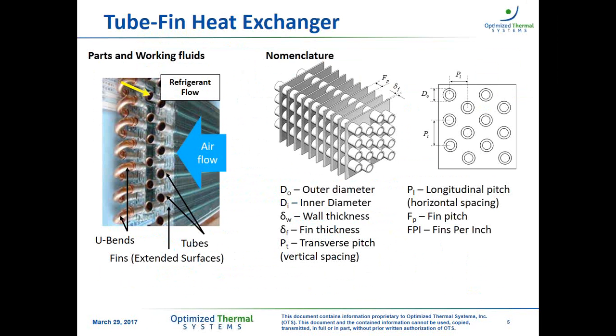So let's start with the definition of a tube fin heat exchanger and the main parts. On the left-hand side, we have a figure of a tube fin heat exchanger cut open, where we can see the tubes, the fins or the extended surfaces where the air flows in between the tubes and the fins, and the refrigerant flows inside the tubes, as indicated by the arrows here. On the right-hand side, we have a nomenclature, just for the record, for your information. I'm not going to spend time on this, but once you have your material in hand, you can always refer to this regarding the parameter naming that we use.